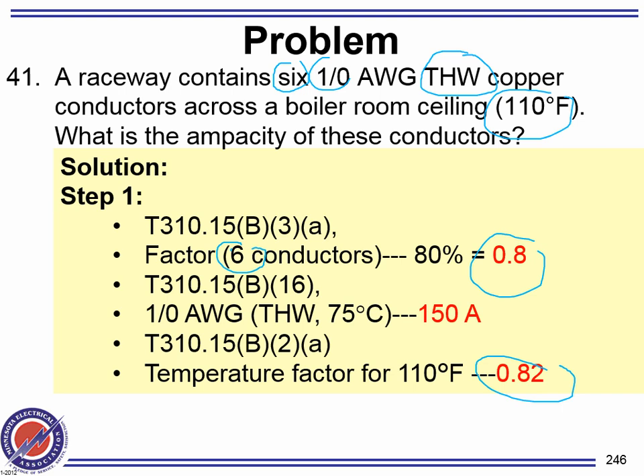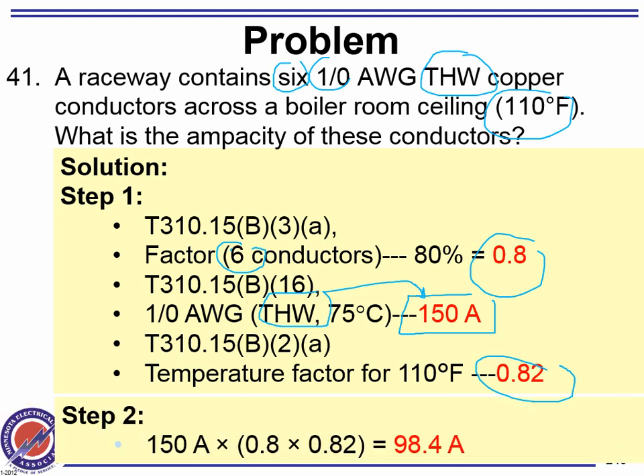And the ampacity of the conductor, because it's THW under the 75 degree column, that would be 150. So then my conductor, under these circumstances, cannot carry more than 98 amps. You can't double derate between continuous load and voltage drop and these. But the bundling and temperature are one thing. This is derating because of bundling and temperature. Yes, we're talking about heat here, but continuous load is a different thing.